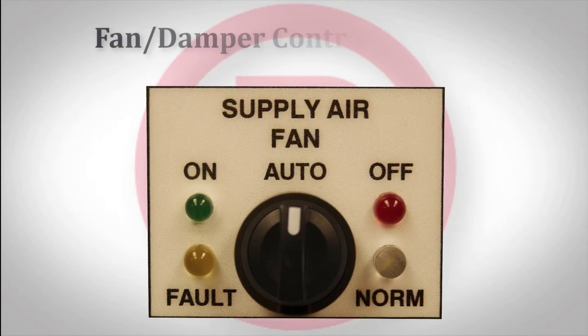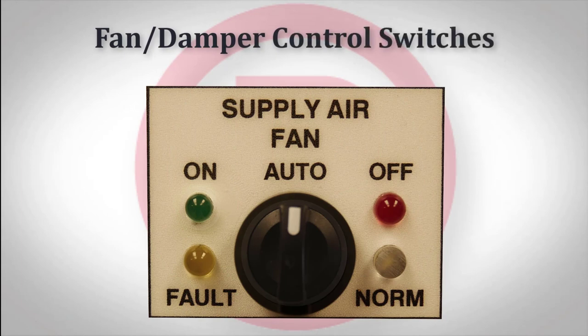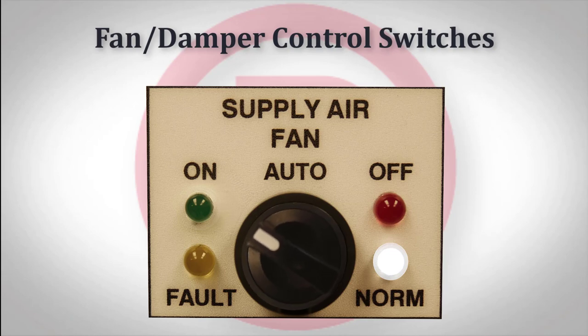The three-position fan and damper control switches will act as follows. When in the auto position, the fire alarm panel controls fan and damper activation, and the normal LED should be illuminated. To manually activate or open the fan or damper, turn the key to the on or open position. Once the panel sees a positive on or open feedback from the fan or damper, the on LED will illuminate.